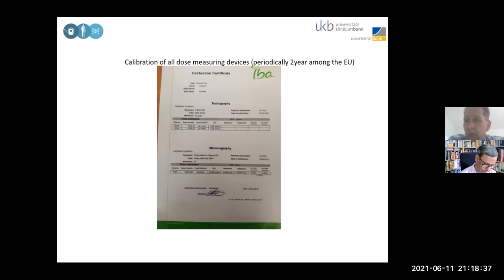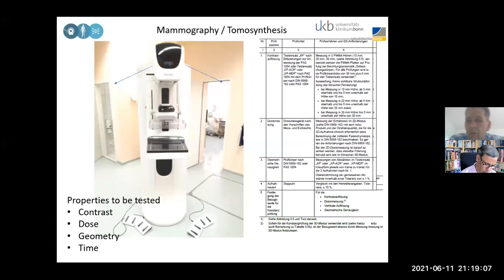Especially in mammography, you will have a hard time measuring with a conventional ion chamber. You have to have an ion chamber which is dedicated to 20 up to 30 kV. And therefore you need a calibration certificate. No matter which vendor, but I can recommend: don't do your ionization chamber measurements or your diode measurements with diodes which are not accepted for energies lower than 30 kV. So check your certificate. So now we come to mammography.